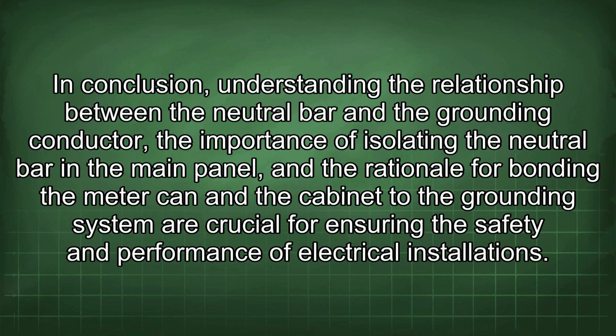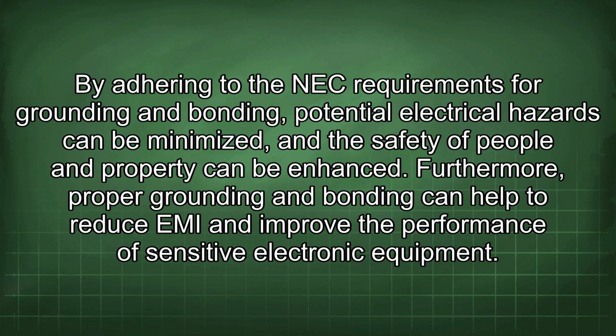In conclusion, understanding the relationship between the neutral bar and the grounding conductor, the importance of isolating the neutral bar in the main panel, and the rationale for bonding the meter can and the cabinet to the grounding system are crucial for ensuring the safety and performance of electrical installations. By adhering to the NEC requirements for grounding and bonding, potential electrical hazards can be minimized, and the safety of people and property can be enhanced. Furthermore, proper grounding and bonding can help to reduce EMI and improve the performance of sensitive electronic equipment.